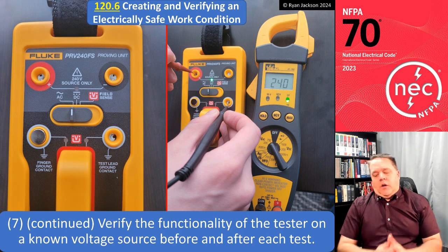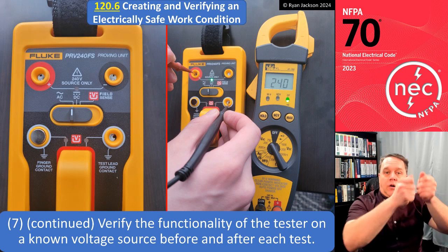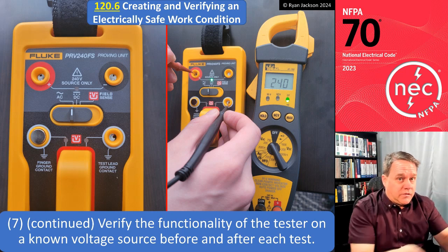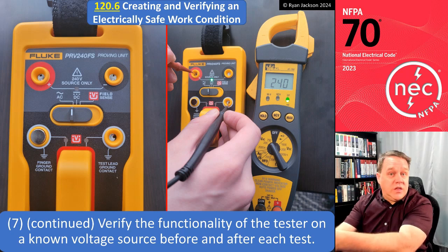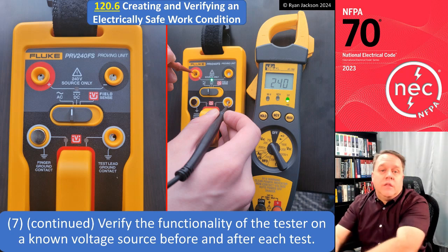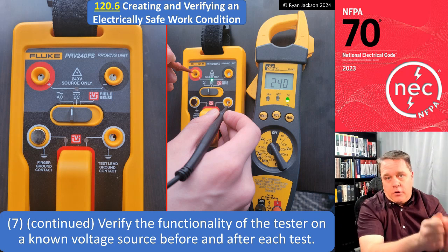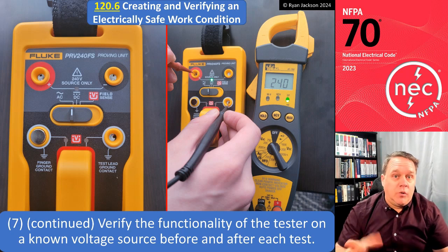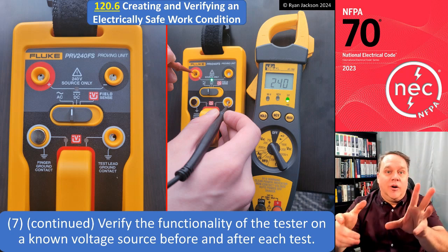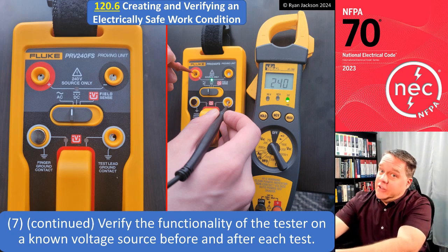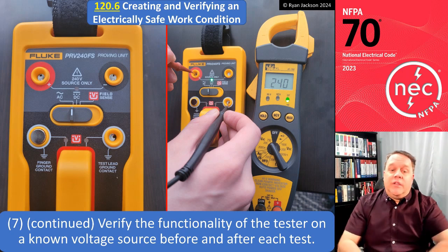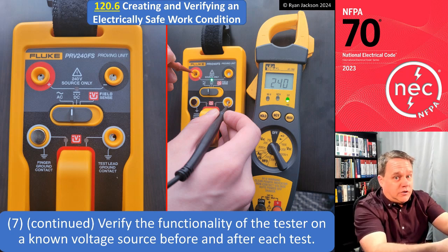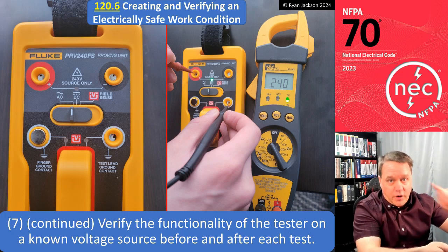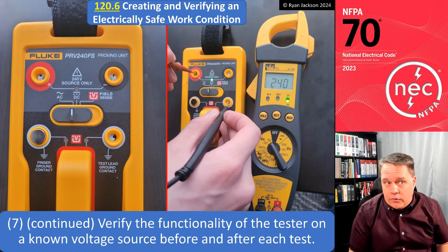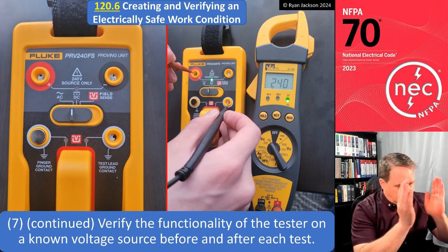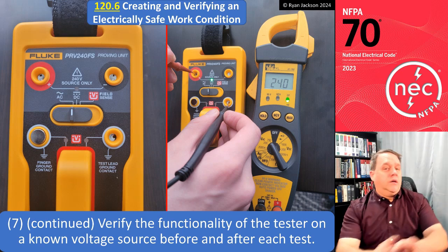So a live, dead, live, right? We're going to check the meter on something we know is on so we can check that the meter works. Then we're going to check and make sure that what we think is off is indeed off. Then we're going to go back and check that the meter still works. Maybe we want to make sure we didn't hit the hold button while the meter was on 0. If you hit the hold button and you test it, and it was actually on and it reads 0, well, then when you go back to test your meter on a known voltage source, if it still reads 0 and you know that what you're testing is on, then we know something went wrong. So a live, dead, live test. Test your tester, test the circuit you're working on, test the tester again.